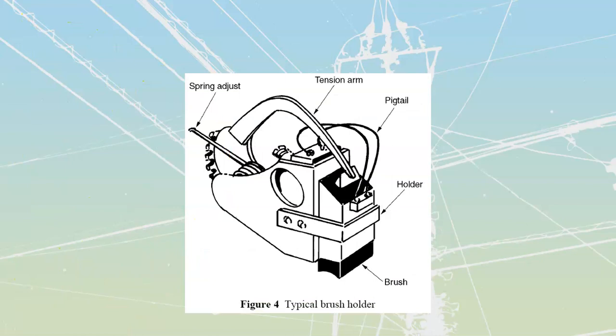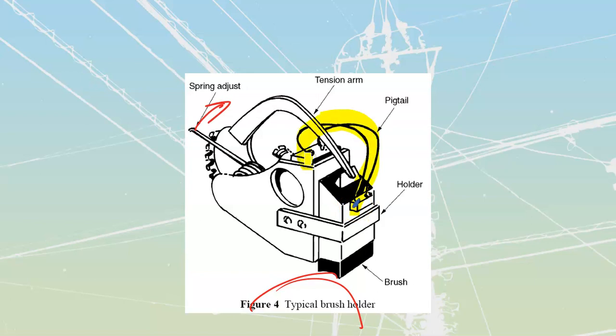That covers our brushes and brush holders. The brush has flexible copper leads permanently attached to it, referred to as pigtails, which give us a connection point for the machine's external wires. A tension arm with a spring drives the brush down to maintain pressure against the commutator. As the brush wears down, you can move a bar to the next notch to push the brush further and maintain the proper pressure.